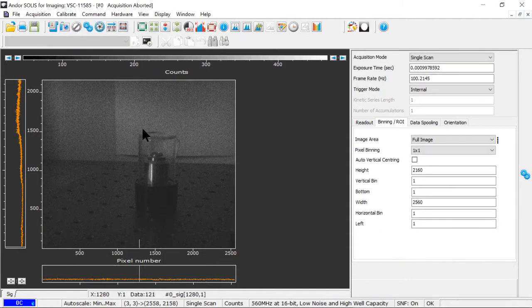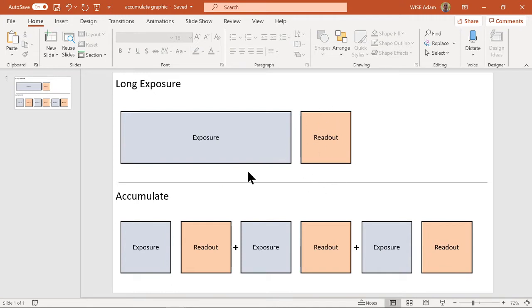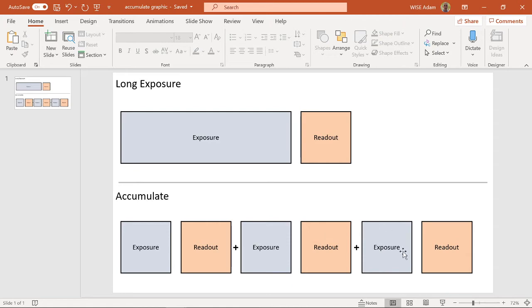I've created a little infographic here that shows the difference. Long exposure is a relatively long period of exposure followed by one readout cycle at the end, and this readout takes some time and generates some noise. For accumulation, there are shorter exposures followed by readout, followed by a shorter exposure, followed by another readout, and so on until you hit the number of accumulations that you've specified.